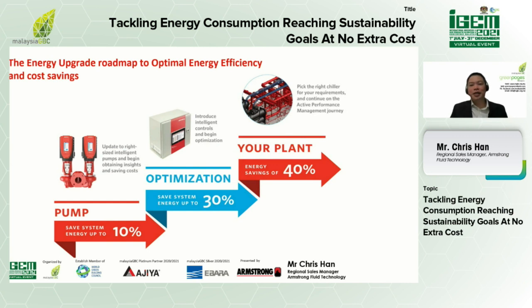A lot of times people tend to zoom in on changing the chiller, since it's the biggest component of energy consumption, looking at more highly efficient chillers. But here, we look at a pump-first approach. Because of how the pump makes system operations transparent to the building automation system, like the heart in our body, it adds efficiency to other equipment by ensuring optimal flow to the chillers and the towers, improving overall operations. Most importantly, with proper planning, breaking the project into smaller sub-projects improves cash flow for building owners.